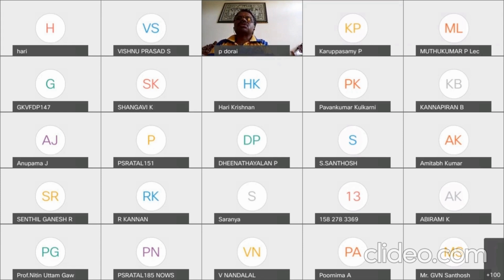It informs the system inside the CPU that all these electrodes are connected, so we can start the operation. If either the return electrode or the active electrode is not fitted properly, or if there is any cut in the cable, it senses immediately and gives an alarm that it is not properly fitted into the socket, thereby preventing burns to the patient.